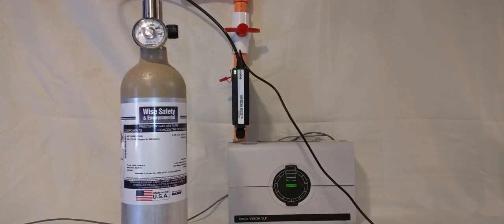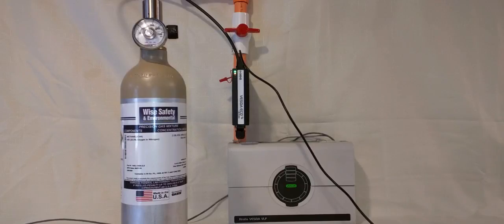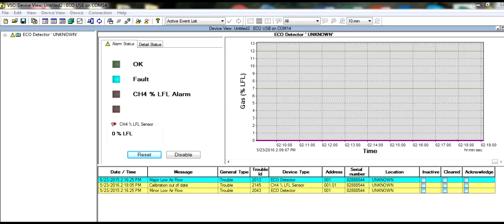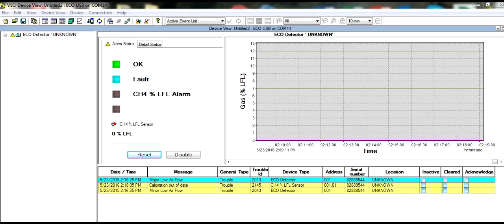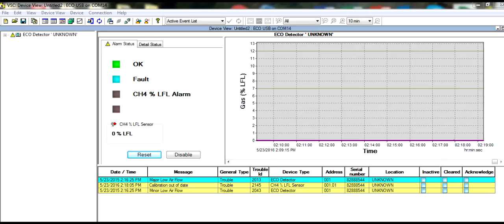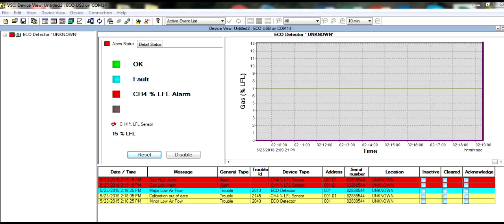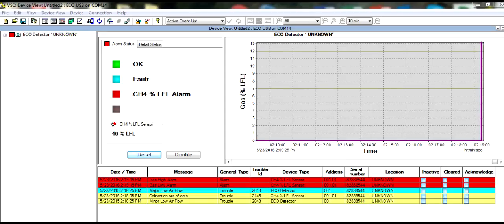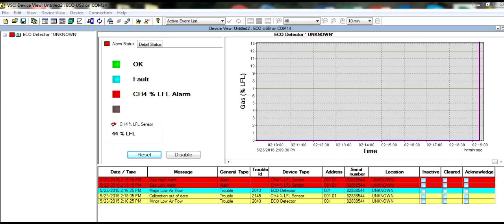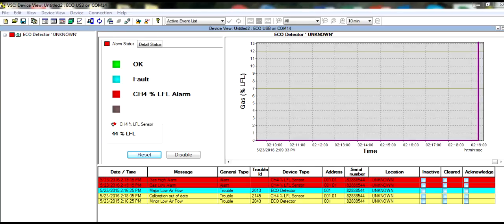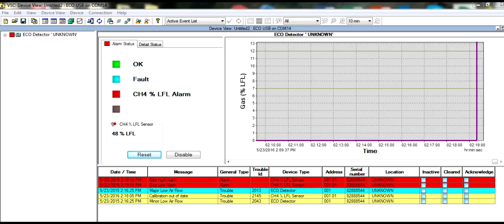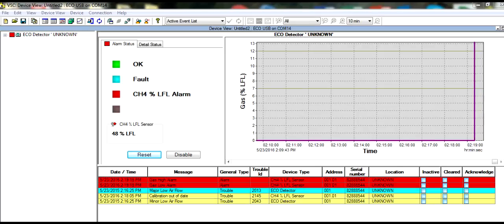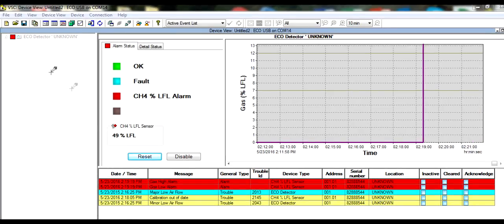Now switch the regulator to the span gas cylinder. In our case, we are using methane at a 50% LFL concentration. At this point, we would bump test the detector before we span calibrate. Open the regulator and allow the gas to flow. As the gas is introduced, the detector goes into alarm. Confirm that alarm output circuits are functioning properly. Even though the detector is going into alarm, we still must span calibrate to clear the span calibration due fault.